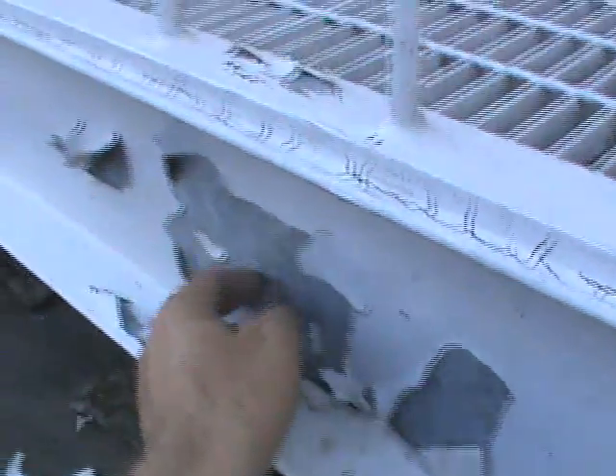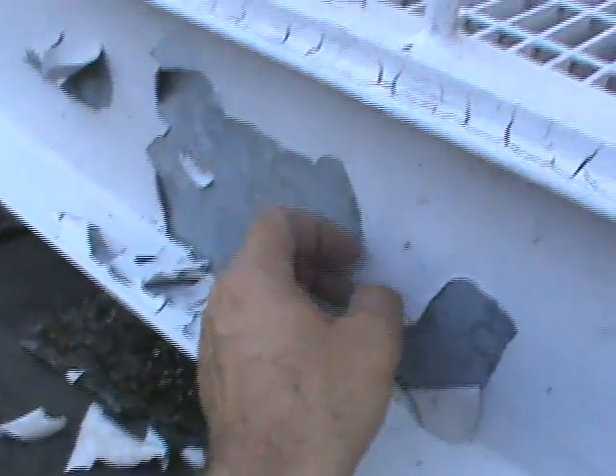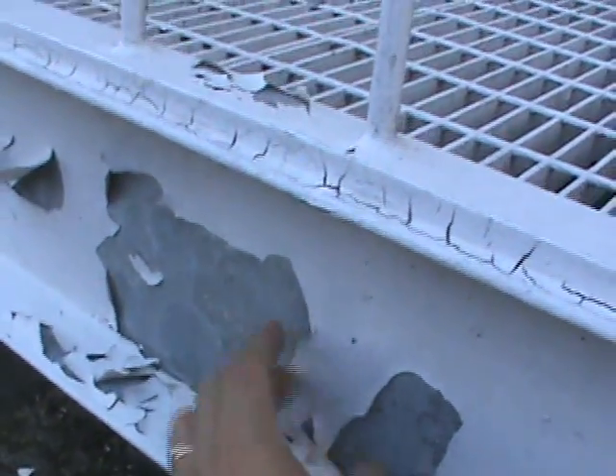All right, this is a fully galvanized fire escape here. So this one we're not going to have a problem with, because the issue is really how it's peeling against the wall. It wasn't properly treated. They probably painted right over it, and you can still see some of the shine. You're supposed to let these things weather one year, and then you can prime it with Galvite, and then you would go to the point of giving it a full paint job, and that's what's going to make these things last 40 to 50 years.